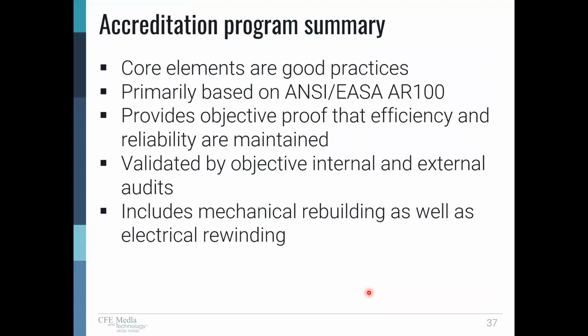So in summary, the accreditation program's core elements are good practices, primarily based on ANSI EASA AR100, and they provide objective proof that efficiency and reliability are maintained during the process of repair, validated by objective internal and external audits. The internal and external audits look for: are we following our steps? Are we going through each of those 70 plus steps and doing it the way it's supposed to be done? In addition, is the equipment used for each of those steps calibrated, and does the calibration record show that the calibration is current? And we're including mechanical rebuilding as well as electrical rewinding.